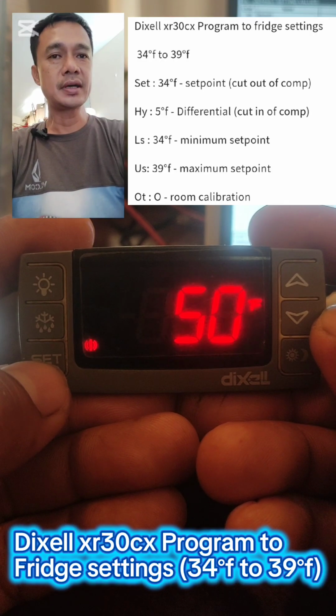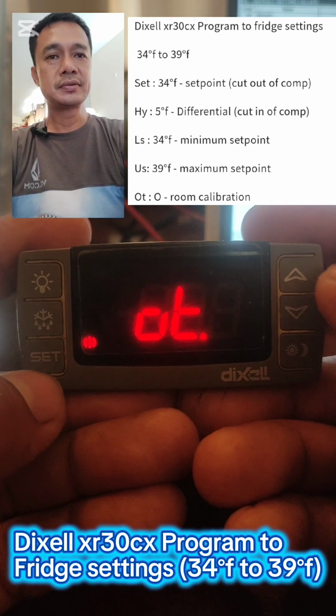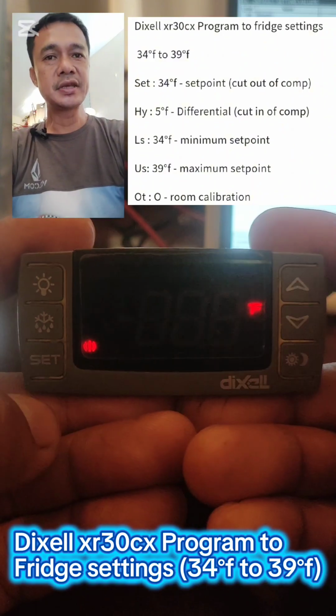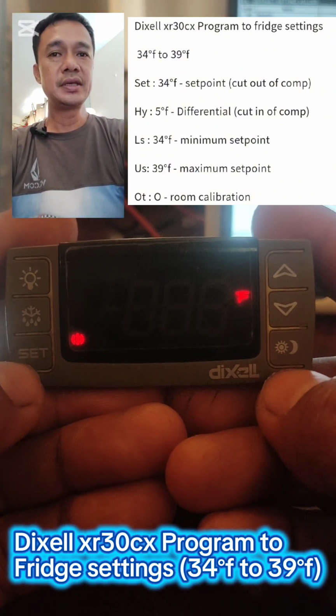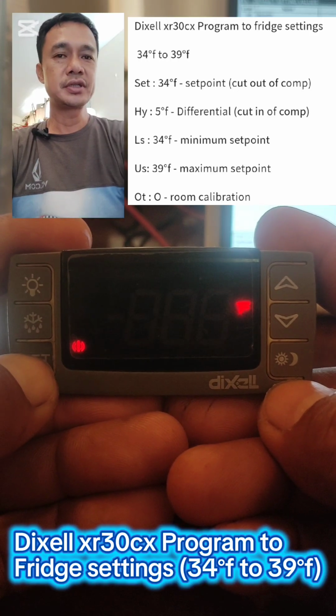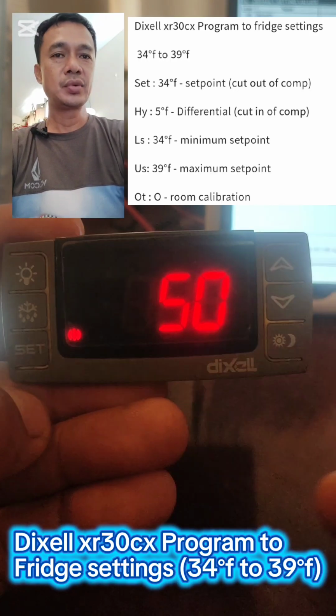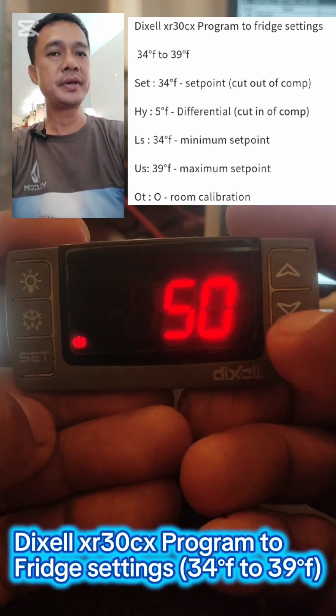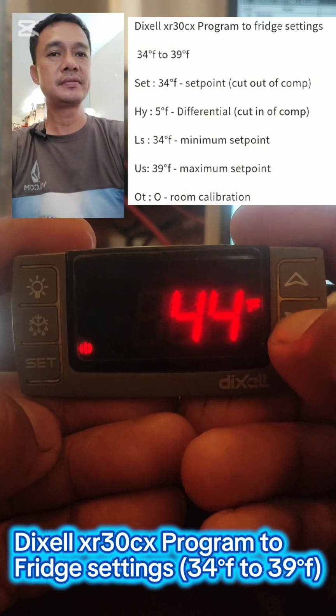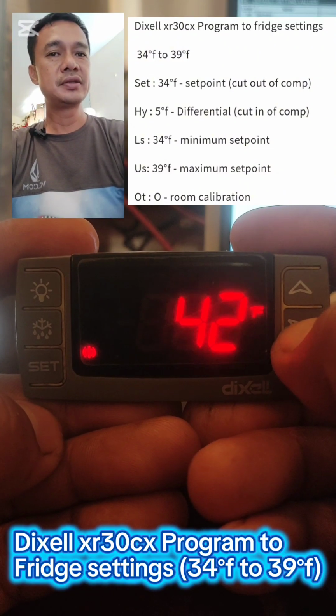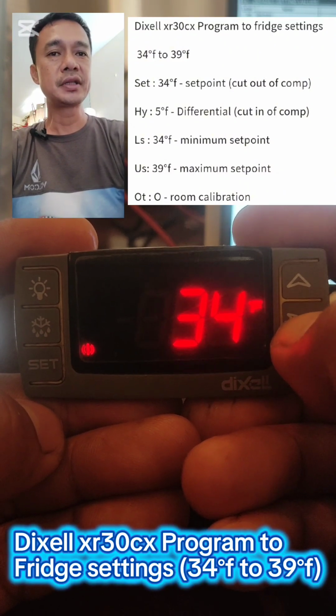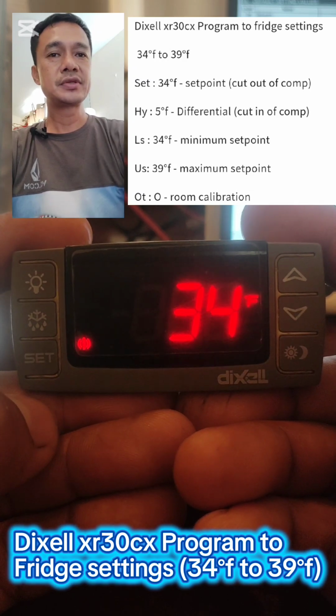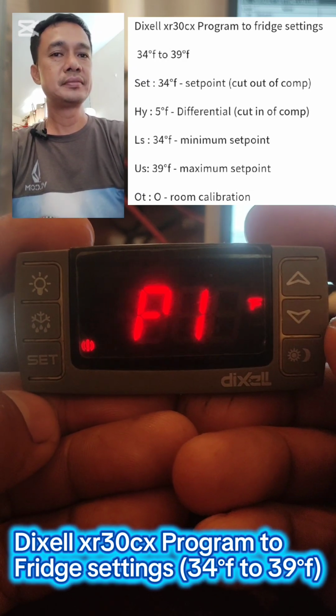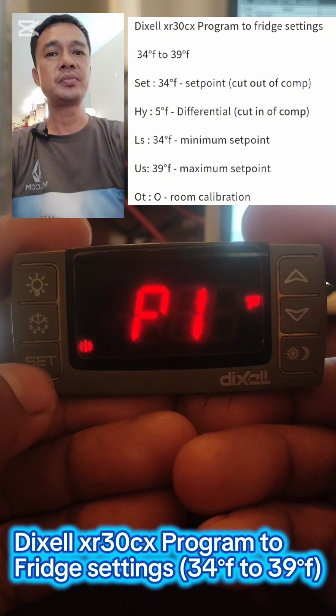We'll go back, or I will just skip here and go to the display so I can change the set point by pressing the set button here. When degrees Fahrenheit appears, we can now change the 50 into 34. So this will be my set point. So my set point is the same as my LS.